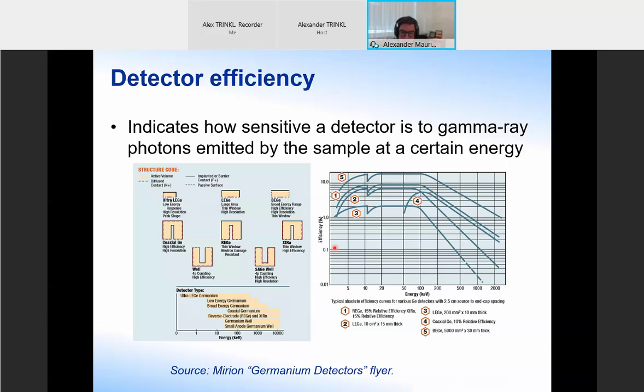There are a lot of different configurations, and when you choose a detector for your laboratory, it's a good idea to think about what your application is, which energies you are looking at, and where you want the detector to be really sensitive. Detector efficiency is a big subject. We will talk about that more in webinar session 3. All I want you to know now is that different types of detector crystals will have different efficiencies at different energies depending on their shape, how the contacts are, how the end cap window is, and so on. We will go into much more detail in the 3rd webinar session. But at least we now know what detector efficiency means. Generally, you would like a high probability of detecting a certain energy of emitted gamma ray in your detector.